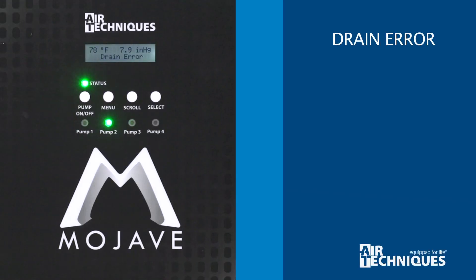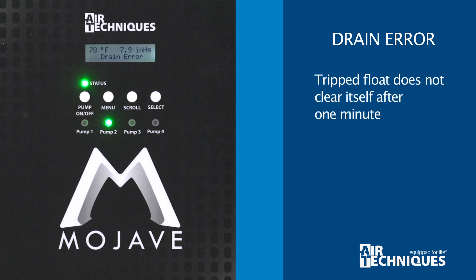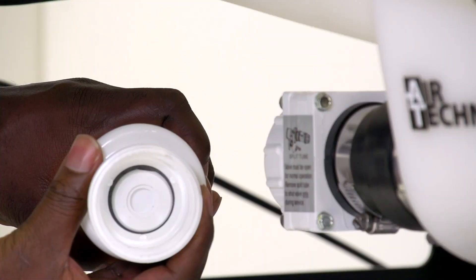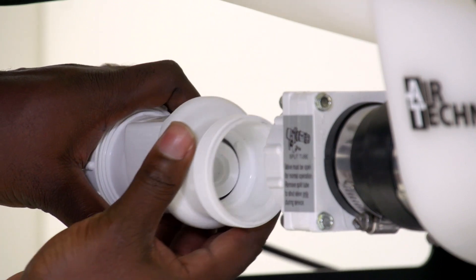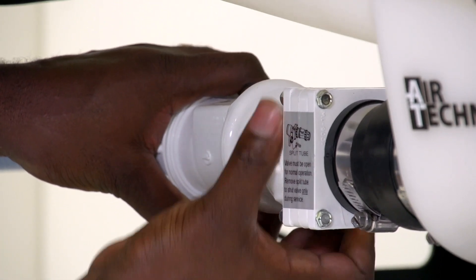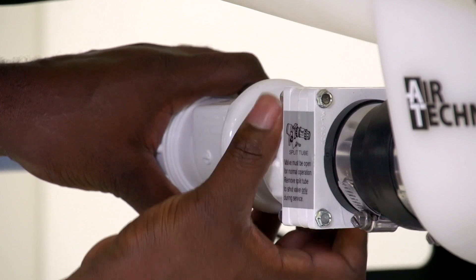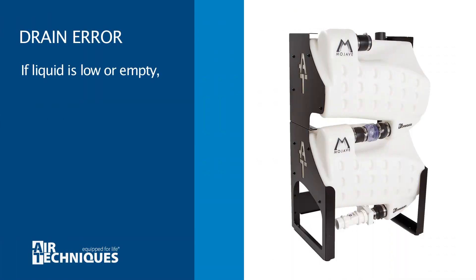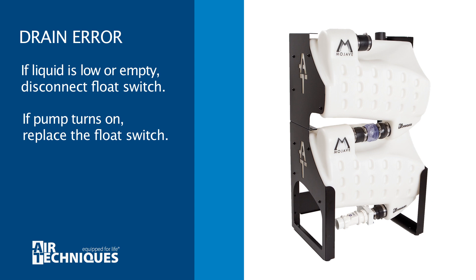The drain error occurs when a tripped float, which shuts all vacuum pumps off, does not clear itself after one minute. Check the liquid level in the tank. If it is high, ensure that the gate valve is open and the tank drain check valve is not clogged. Open the valve and/or fix the clog and allow one minute for the tank to drain — the pumps should turn back on automatically. If the liquid level is low or the tank is empty, disconnect the bottom float switch. If the pump turns on, the float switch must be replaced.